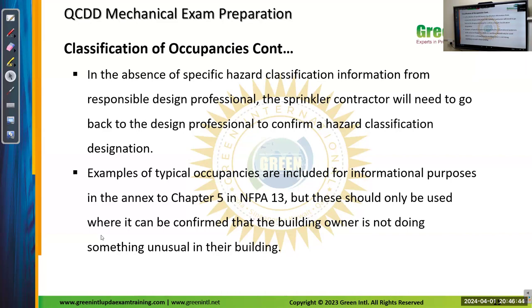In the absence of specific hazard classification information from the responsible design professional, the sprinkler contractor will need to go back to the design professional to confirm the hazard classification designation. Examples of typical occupancies are included for informational purposes in the annex to chapter 5 of the 2013 edition, but these should only be used where it can be confirmed that the building owner is not doing something unusual in their building. If we identify the hazard level, like this is all mercantile occupancies or educational occupancies, but the owner is renting it out for a printing machine, the hazard level changes, right? If they rent it for paint storage, the hazard level changes. So whatever is intended for the identified hazard group, only that is to be used.